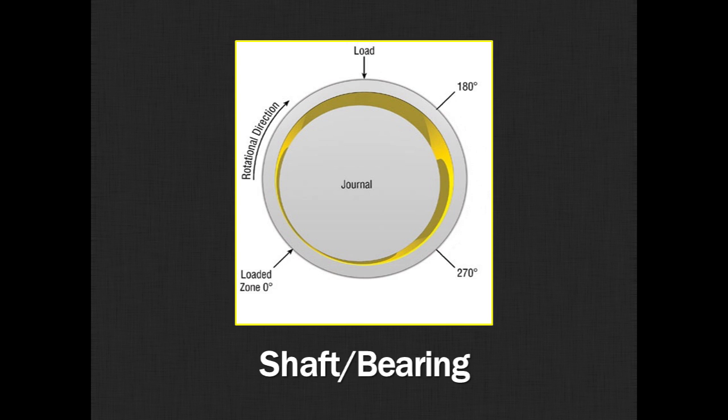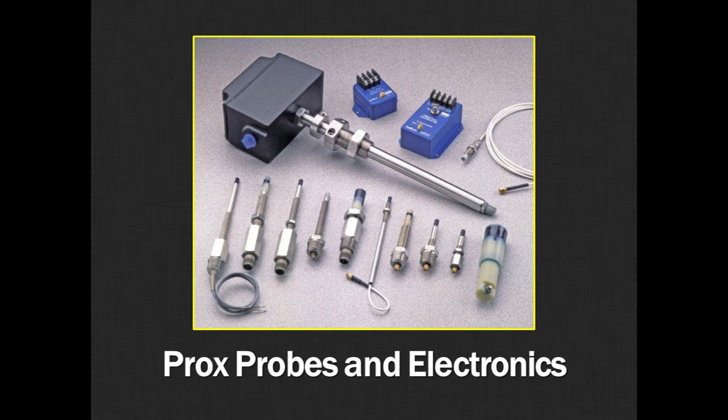So we use eddy current proximity probes for doing contactless measurement in these kinds of applications. So they can measure very small distances with no contact, no moving parts. They work in harsh and dirty environments and they basically do the job and run forever. We're talking about making very small measurements here, measurements that are typically less than a tenth of an inch and in many cases it's down to the thousandth of an inch.